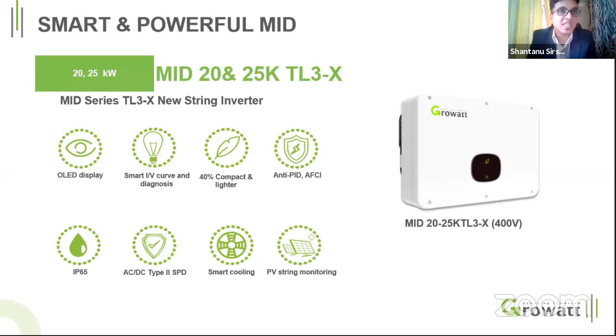This inverter gives you a maximum efficiency of 98.75%, and you can go with a DC overloading of around 30% more, and you can also get an AC overload of 10% on your AC side. So a 20 kilowatt inverter with sufficient DC overloading can give you an AC output of 22 kilowatt.